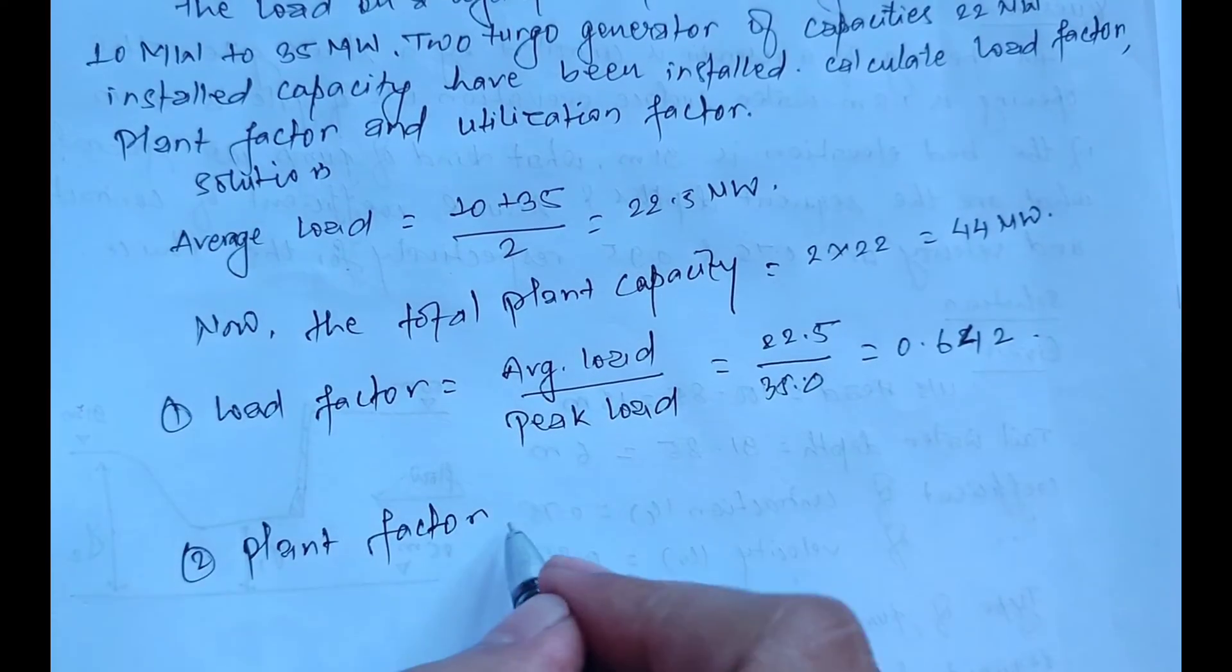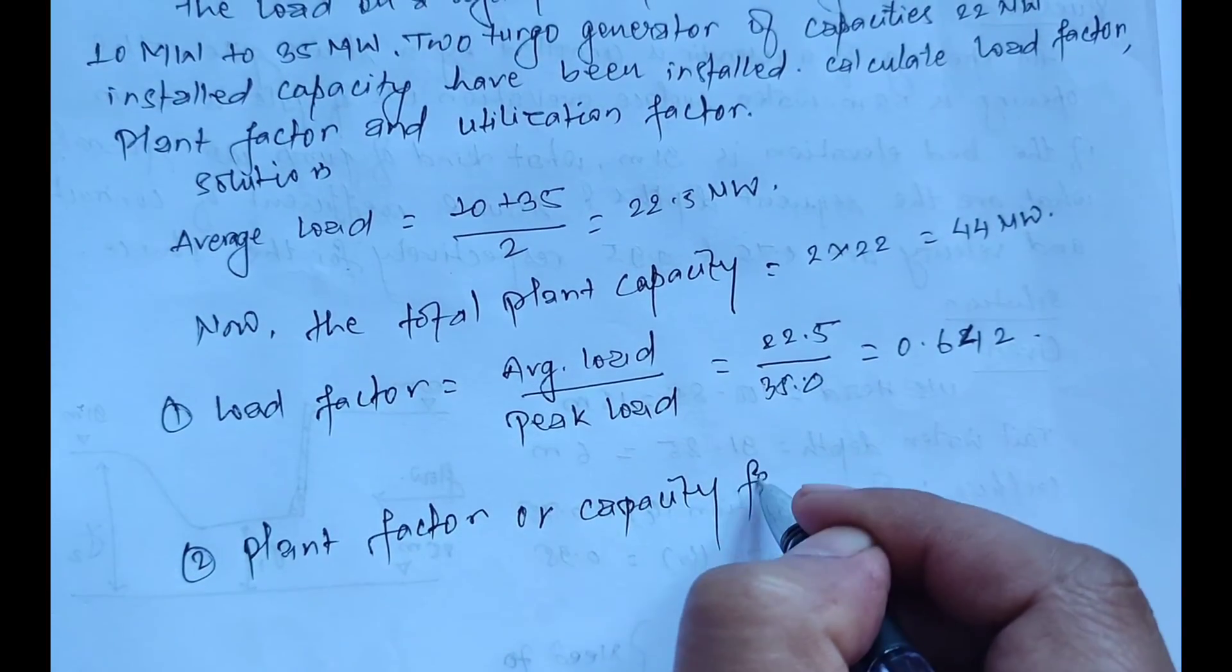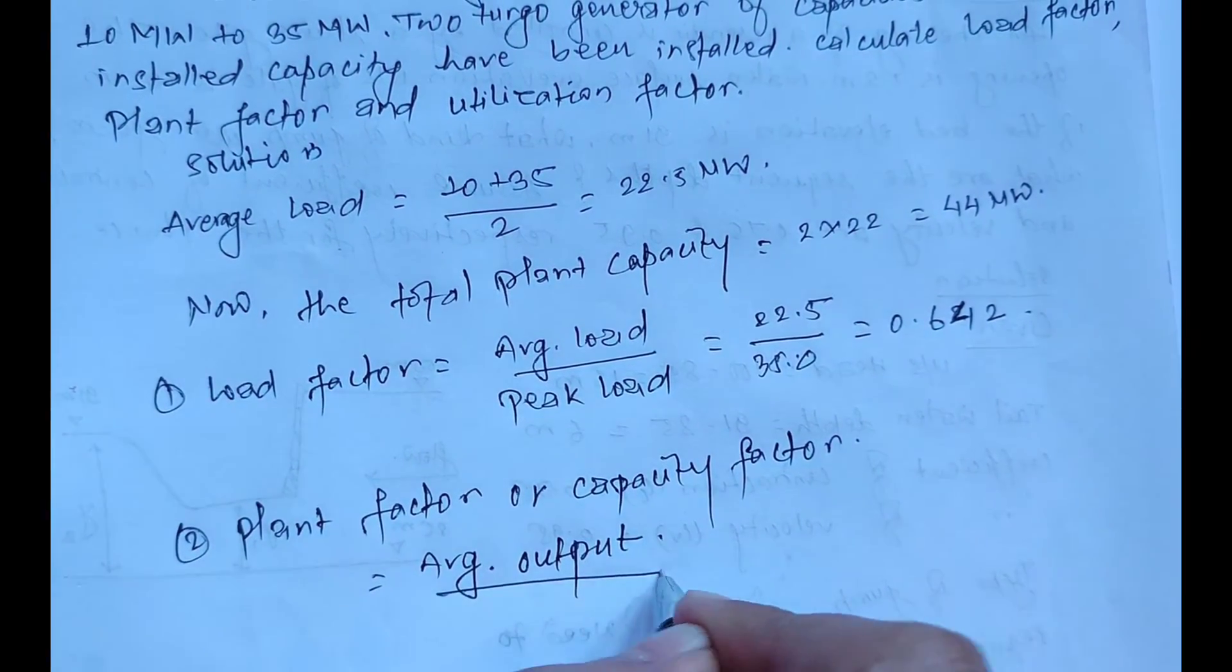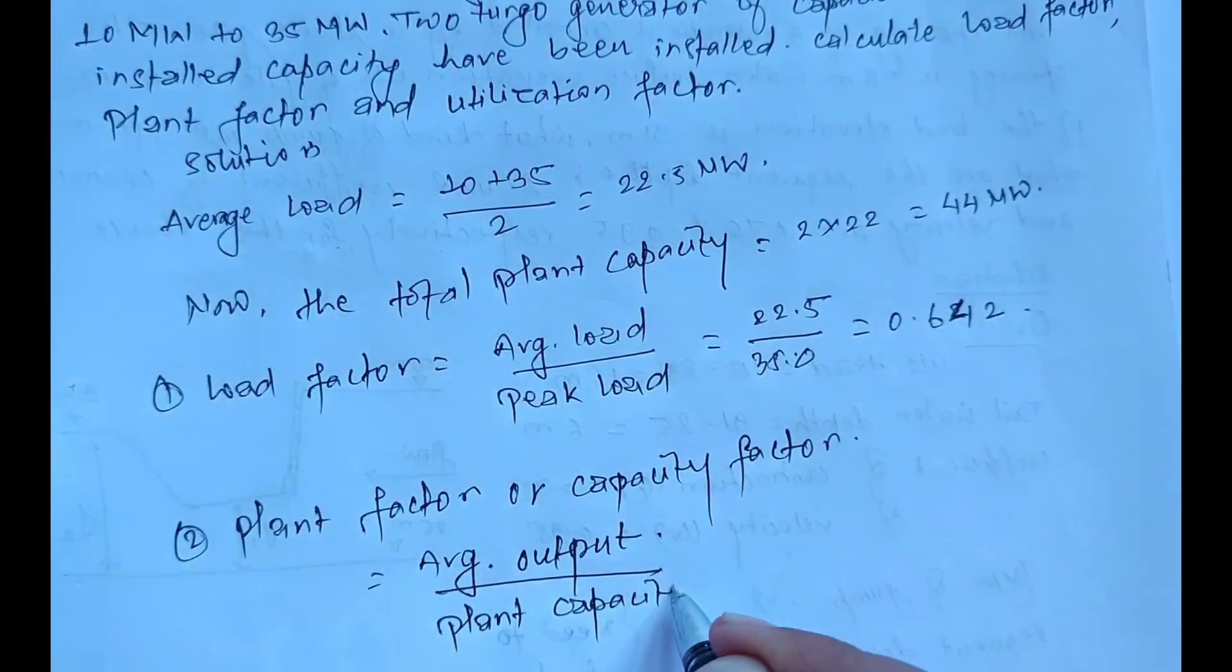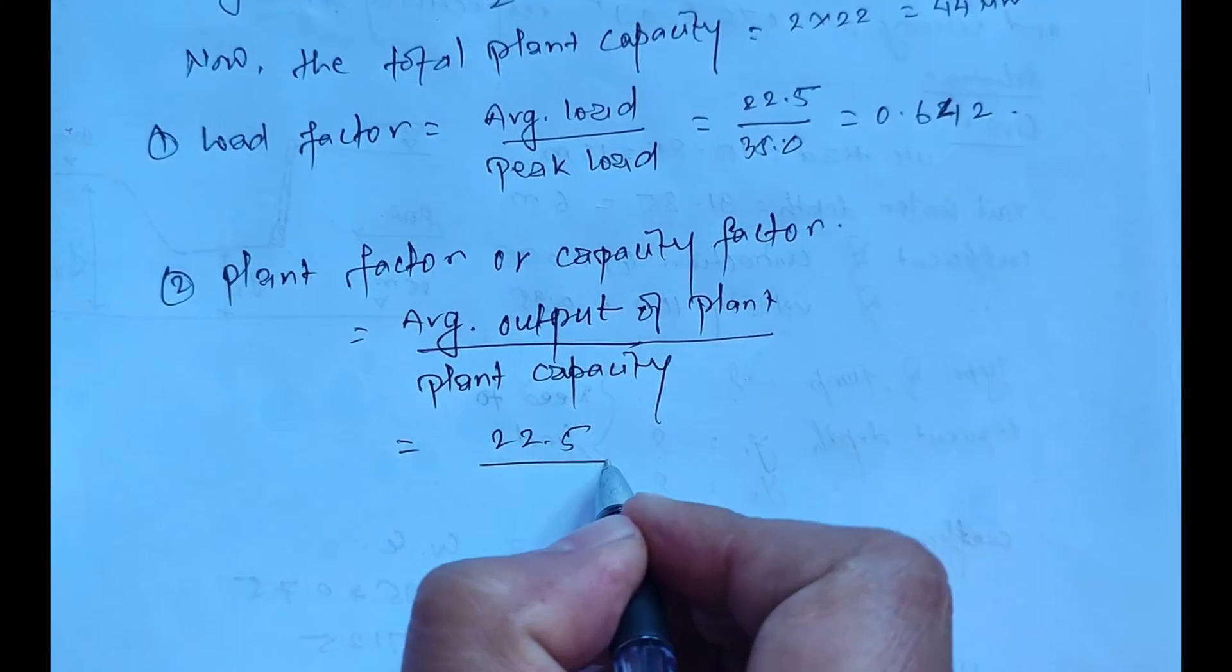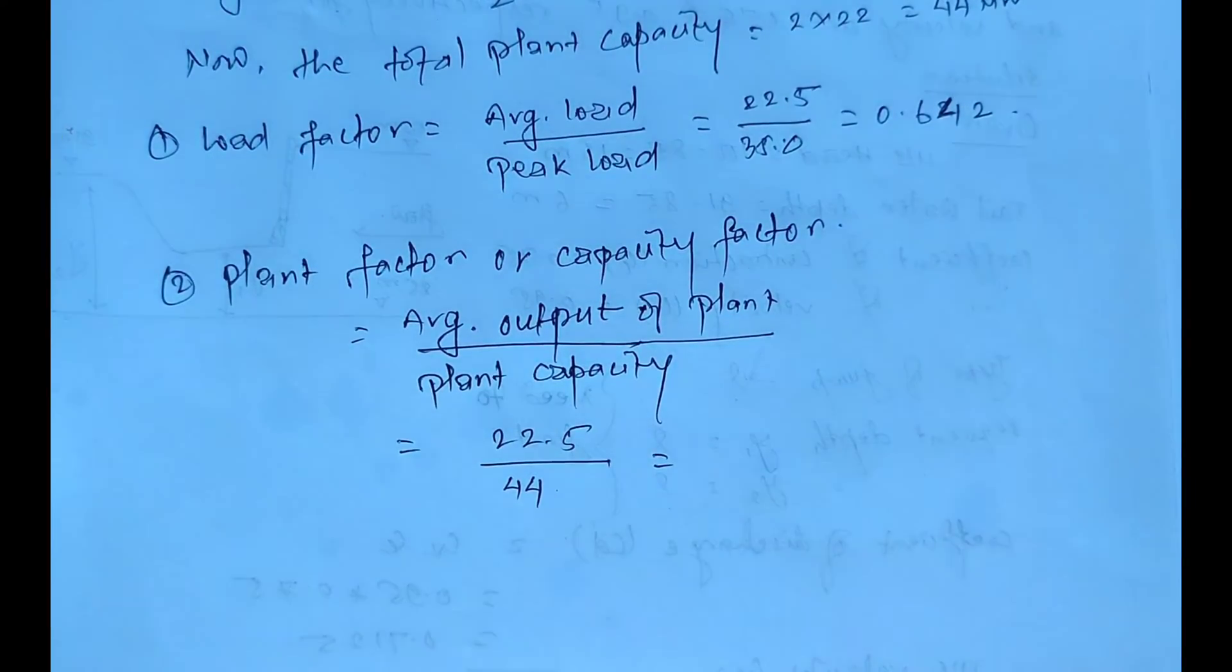plant factor. Plant factor is also called capacity factor. Capacity factor equals average output of plant divided by plant capacity. The average output of plant is 22.5 divided by the plant total capacity of 44 megawatts, which equals 22.5 divided by 44, which is about 0.511.